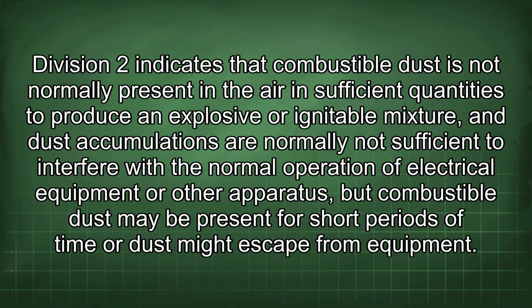Division 2 indicates that combustible dust is not normally present in the air in sufficient quantities to produce an explosive or ignitable mixture, and dust accumulations are normally not sufficient to interfere with the normal operation of electrical equipment or other apparatus, but combustible dust may be present for short periods of time or dust might escape from equipment.